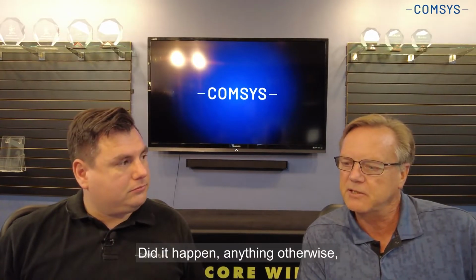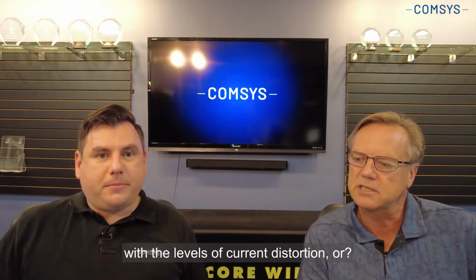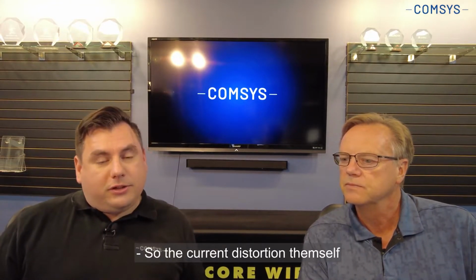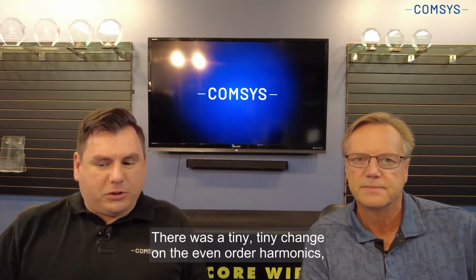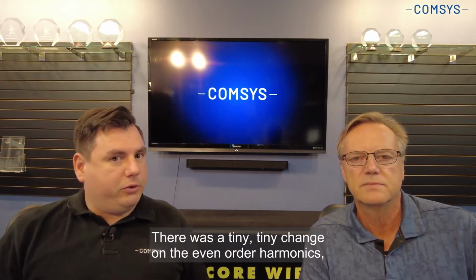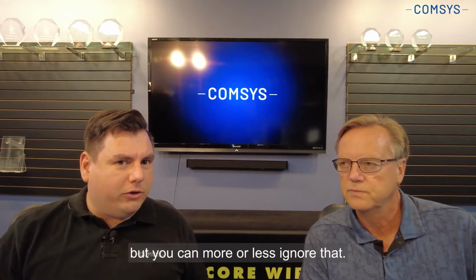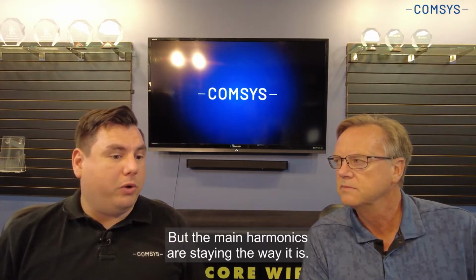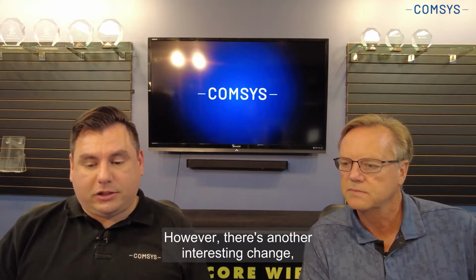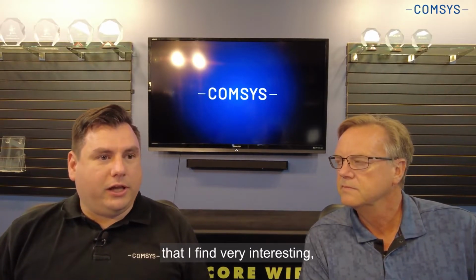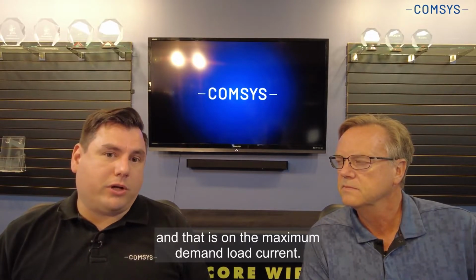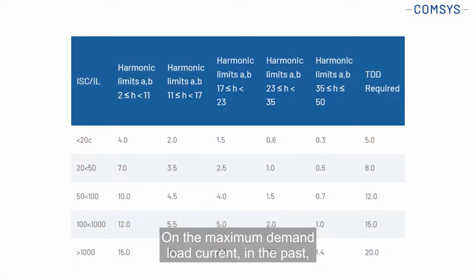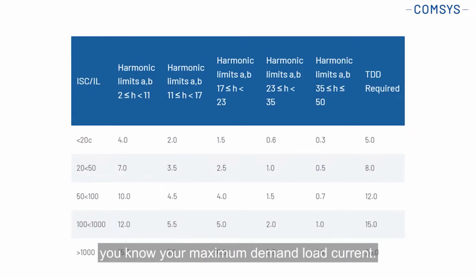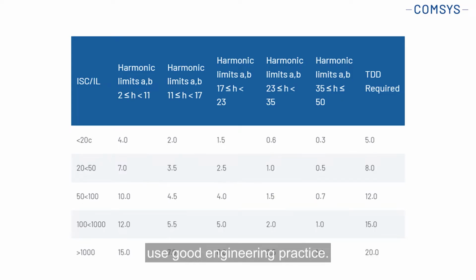Did anything happen otherwise with the levels of current distortion? The current distortion limits themselves did not change very much. There was a tiny change on the even order harmonics, but you can more or less ignore that. The main harmonics are staying the way they are. However, there's another interesting change, and that is on the maximum demand load current. In the past it simply said you need to measure for 1 year, and after 1 year you know your maximum demand load current. For new installations they just said to use good engineering practice.